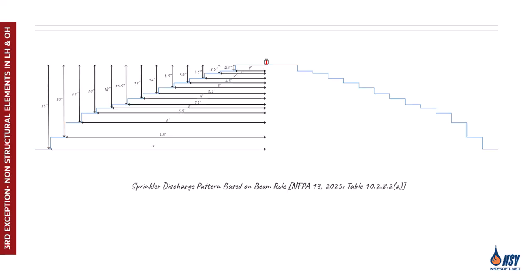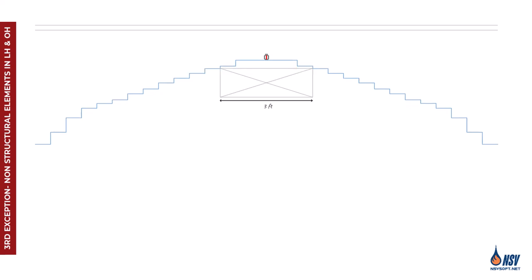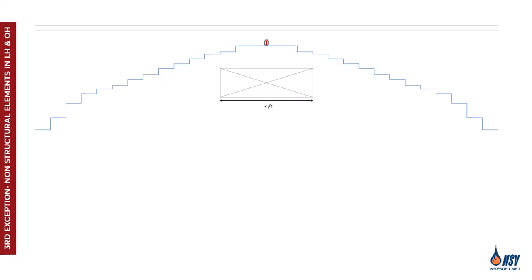While the discharge pattern depends on available pressure, it can be approximated by applying the beam rule table along with the corresponding A and B values, allowing us to visualize the expected spray coverage. As shown in this figure, the sprinkler is installed just above a three-foot wide duct. When we visualize the discharge pattern, it's clear that the duct interferes with its proper formation. By installing the sprinkler closer to the ceiling, the impact of the obstruction on the spray pattern can be reduced.